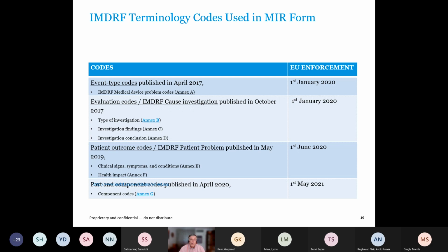A very practical example of that: if you have, for example, a pacemaker, and this pacemaker uses a battery which is also used by other pacemaker manufacturers, and this is very frequent. If the serious adverse event report tracks to this battery manufacturer and battery batch number, the authority will be able to cross-check and to identify if there are some other manufacturers which may be affected by the same failure. So this is what is in place now.